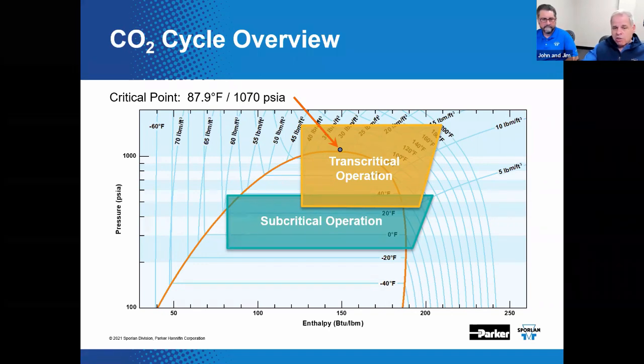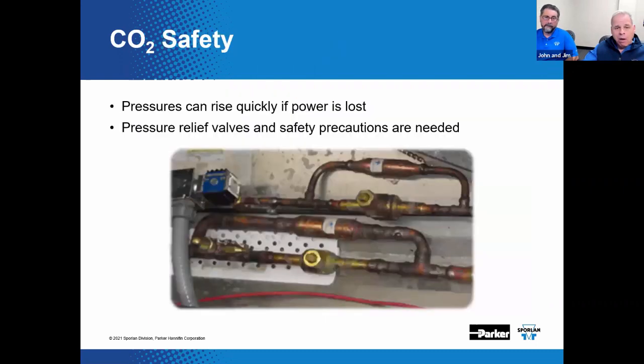To make sure the CO2 temperatures and pressures remain manageable and operating in the subcritical range during even the highest ambient conditions, the HFC-based equipment is required in order to maintain subcritical operation. Yep. Wow. For a truly subcritical system, that's pretty much what's required. Or you need to be in a very, very cool climate. Yeah, so where it never gets above 88 degrees. That's right. Like, not around here.